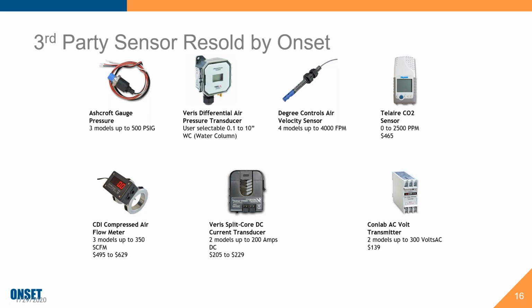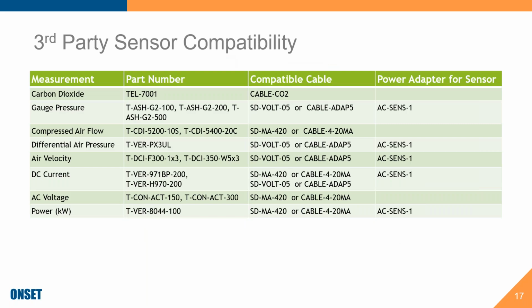If you look at the tip of the old sensors, there's 2 rings around them on the metal part. There's 3 on this one, and that extra ring allowed us to do the self-describing feature. Even though I've plugged old sensors into new loggers, and new sensors into old loggers, and they do plug in, sometimes they look like they work, but 9 times out of 10 they don't. So I would not plug your new self-describing sensors into the older UX or U-series loggers. Even though they fit, I can't guarantee they're going to work.